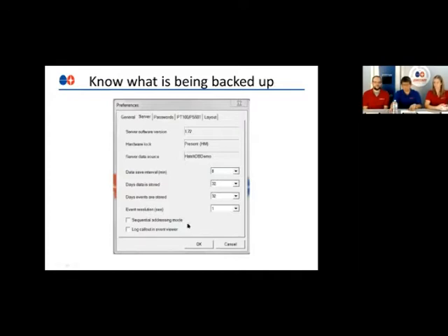The default number of days stored is 32 days in our Hatchcom setup, in which case your backup must be done on the 30th or 31st day of each month. Don't forget to back up, because after the 32nd day, the database will start to get overwritten. You may want to know how much data your machines have collected in 1 month to give you an idea if your hard drive size is more than enough.